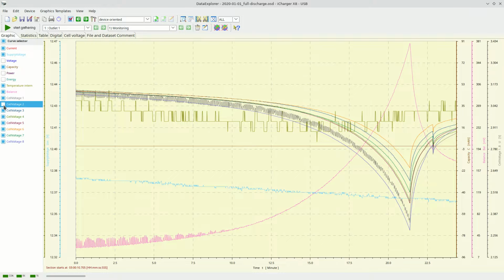This is this color line, see? So what happened: BMS disconnected at 2.3 volts, and in this case the UPS, next time AC is recovered, will start in failure mode. It will not wake up automatically and will not connect AC voltage to the output to power your load. So that's the problem, avoiding BMS disconnection when the battery is fully discharged. You see that at that point the difference between cells became up to 400 millivolts, which is quite high.